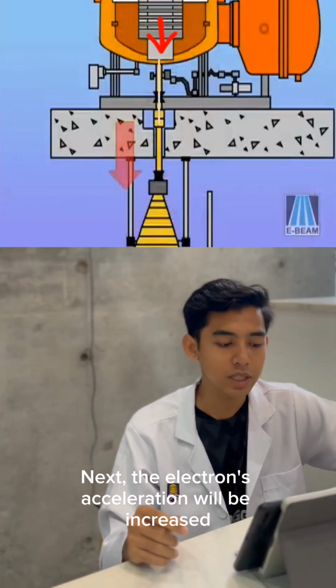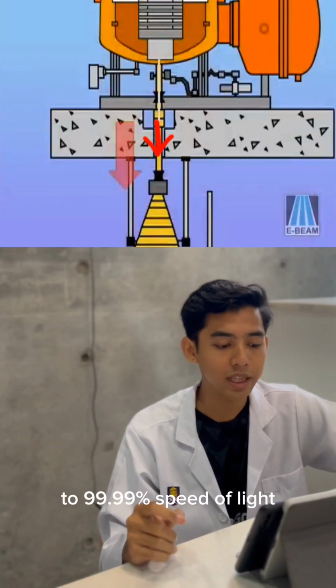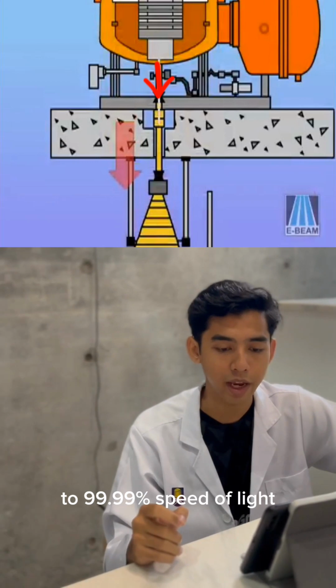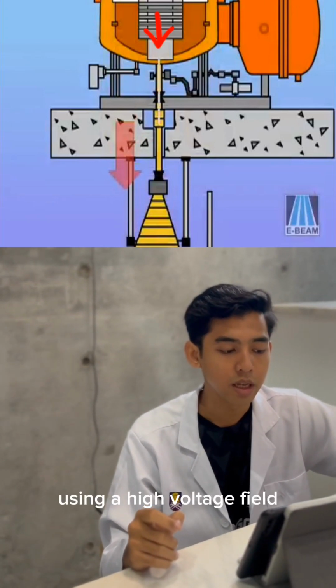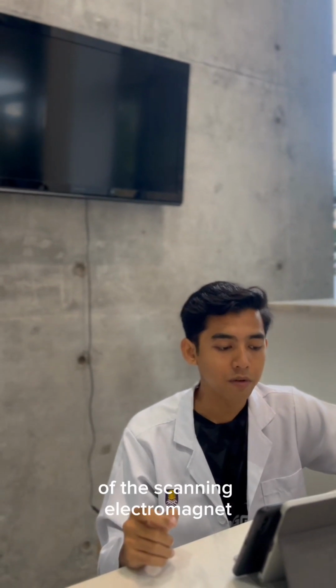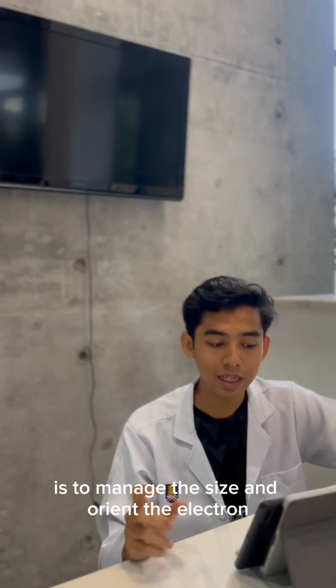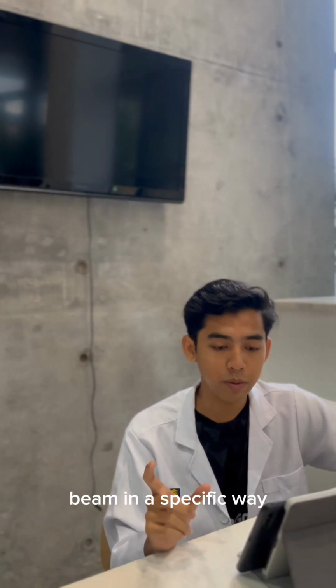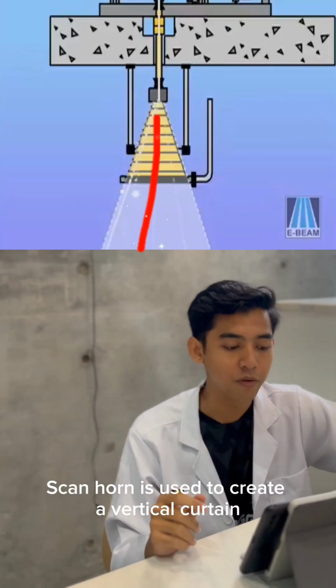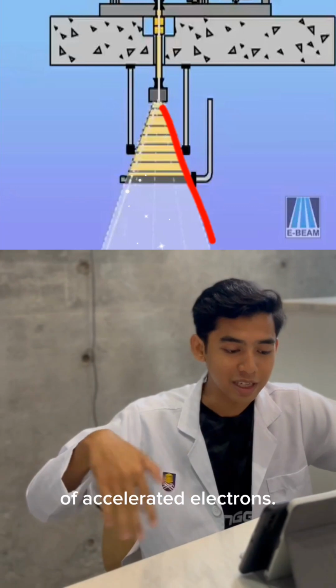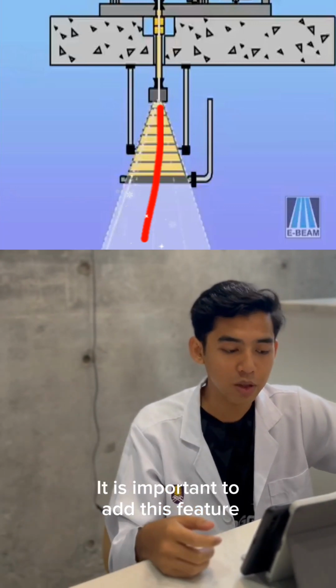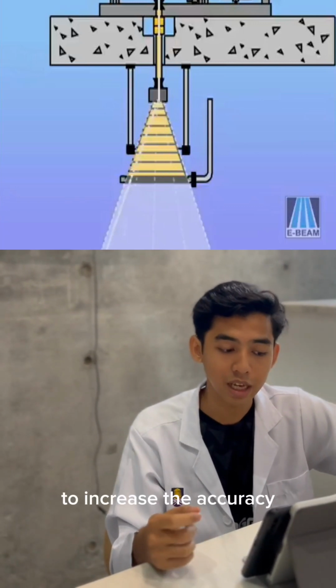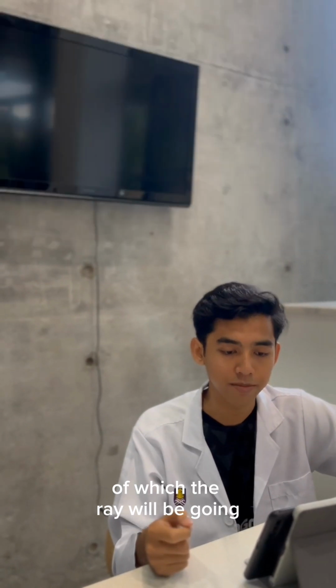Next, the electron's acceleration will be increased to 99.99% of the speed of light using a high voltage feed and pass through a vacuum tube. The installation of the scanning electromagnet is to manage the size and orient the electron beam in a specific way. A scan horn is used to create a vertical curtain of accelerated electrons. It is important to add this feature to increase the accuracy of where the ray will be going.